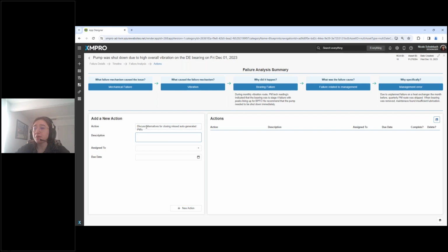So we want to identify why the PM was missed. And some notes here: because this was missed, we need to discuss with maintenance how to mitigate this in the future. I guess the current practice is that the PM is closed and we wait for the next one to come along. But for certain PMs, especially ones like this, that can't be the current practice.